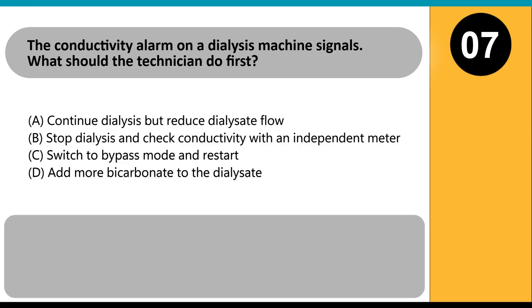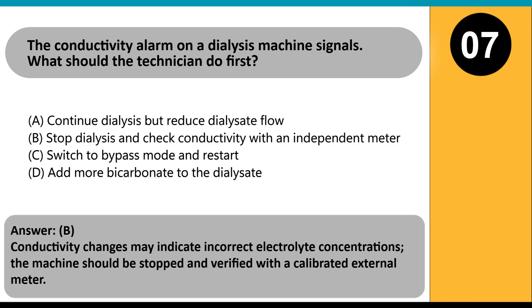The conductivity alarm on a dialysis machine signals. What should the technician do first? A. Continue dialysis but reduce dialysate flow. B. Stop dialysis and check conductivity with an independent meter. C. Switch to bypass mode and restart. D. Add more bicarbonate to the dialysate. Answer B. Conductivity changes may indicate incorrect electrolyte concentrations. The machine should be stopped and verified with a calibrated external meter.